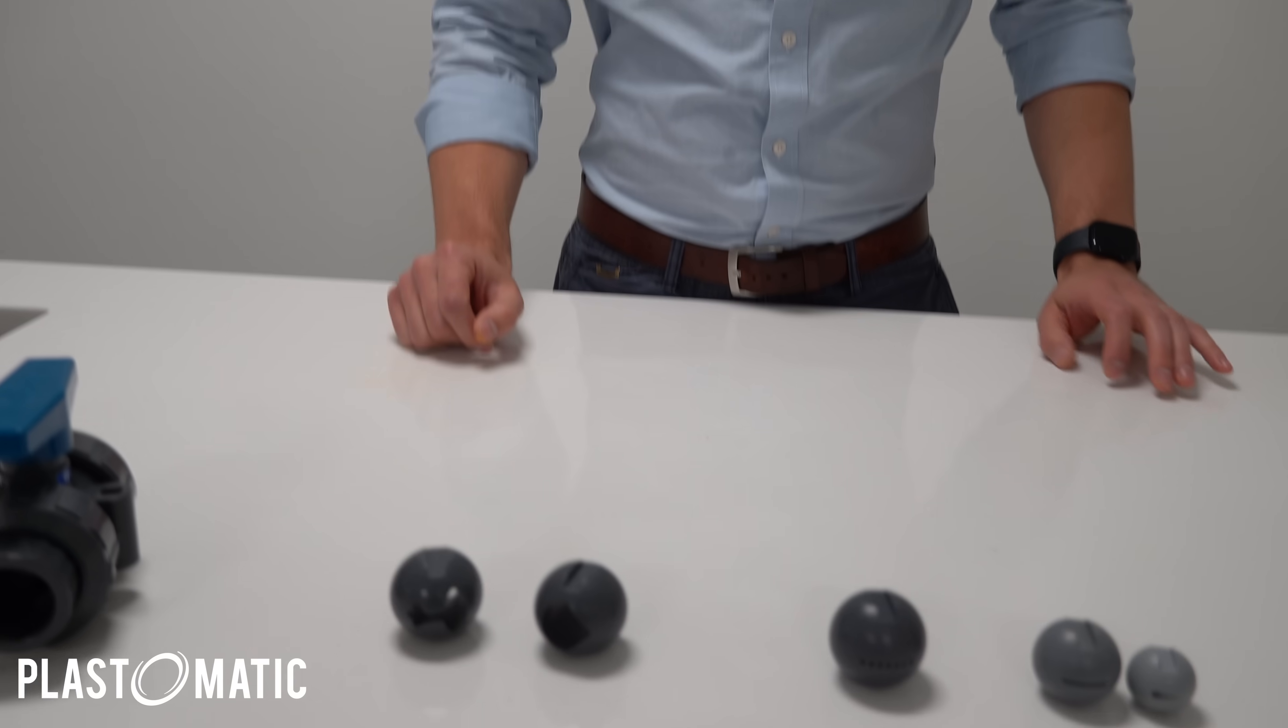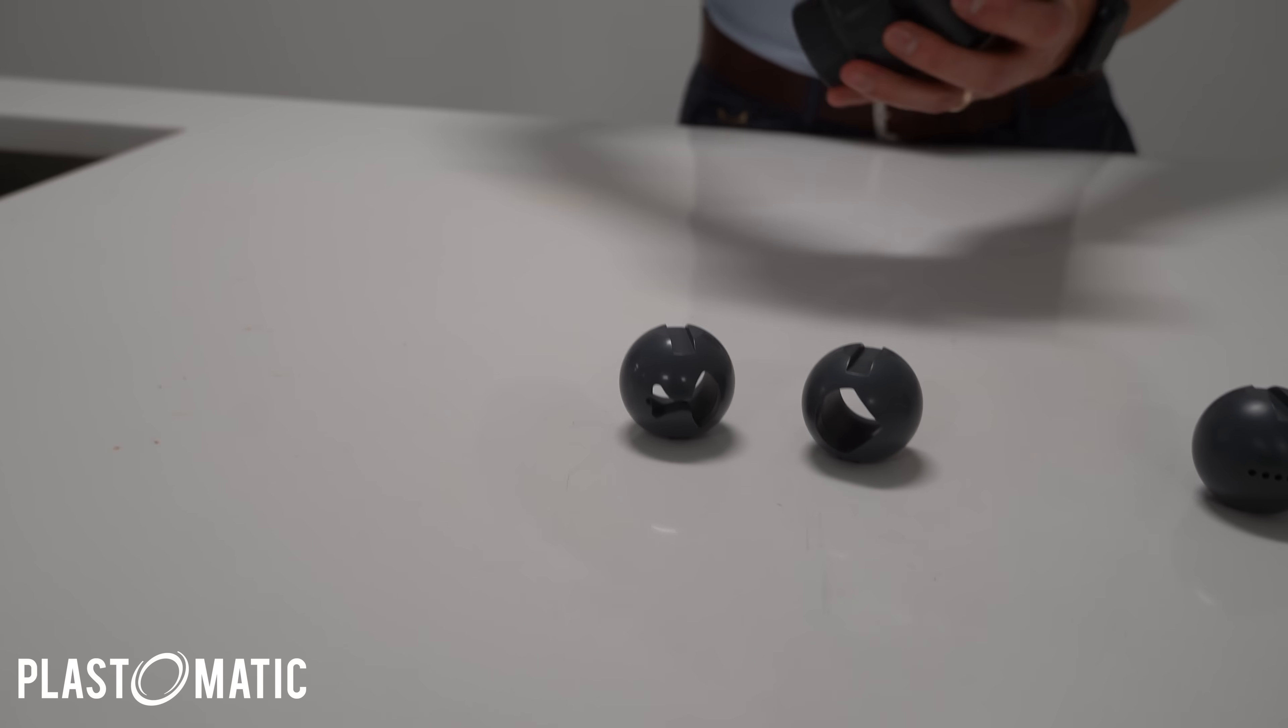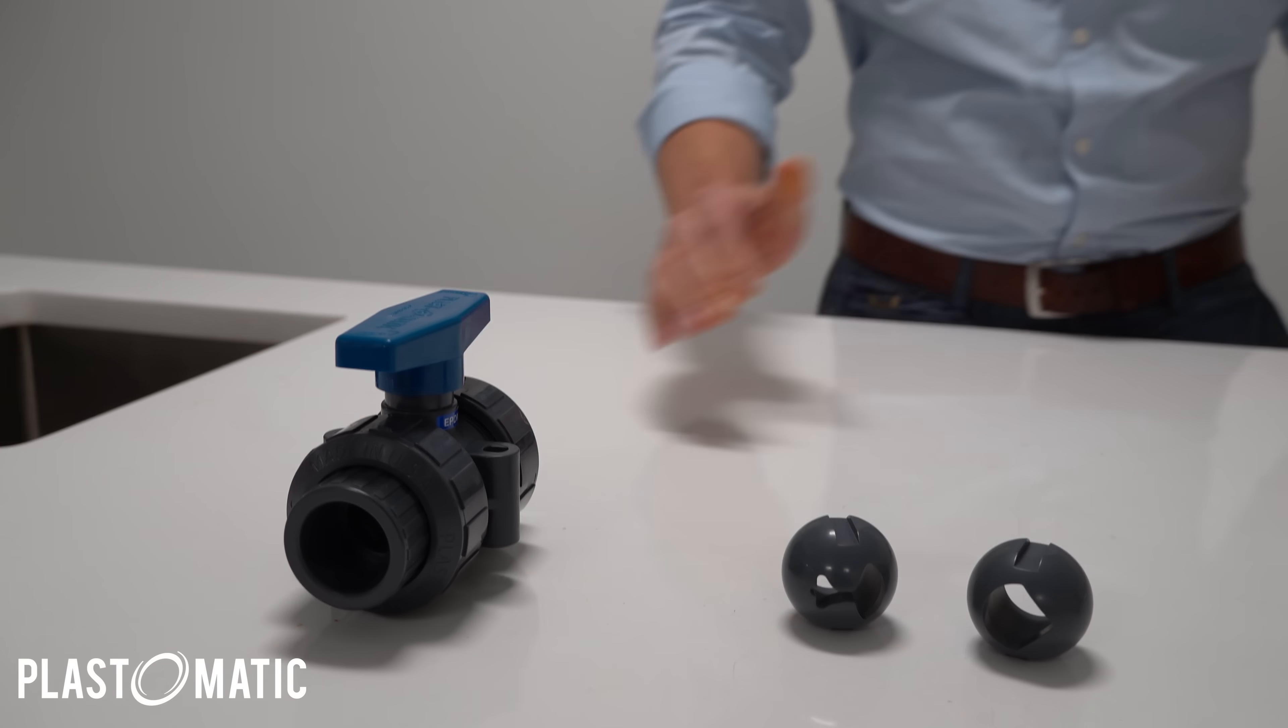So a linear flow ball, essentially what it will do is, as you turn the handle towards open, the 90-degree turn, your flow curve, if you were to graph it, will be exactly linear. So if you had a full-port ball, this might be way too much flow and you might not be able to dial it in as perfectly as you would like to. So using a characterized ball, the flow curve is just much more predictable, much more linear, so you're able to dial it in pretty much by degree open. You should expect this amount of flow.